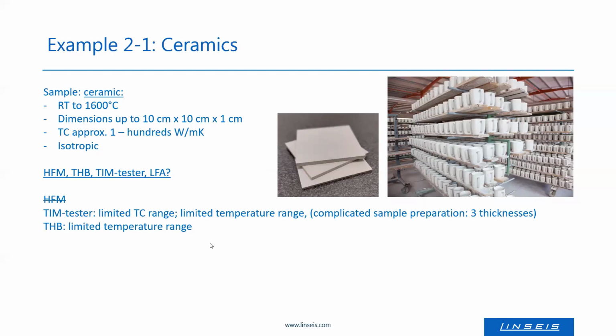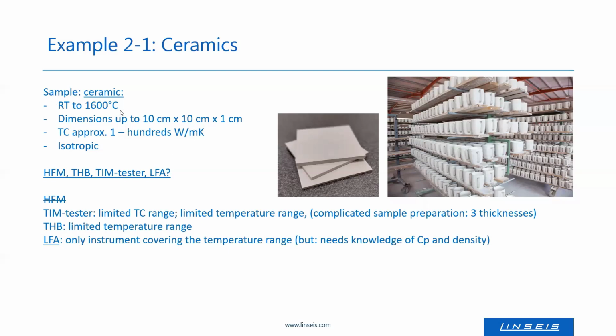THB will not cover the temperature range either, so the laser flash instrument is the only instrument covering the complete temperature range and can handle the dimensions, or you can prepare samples from these blocks which fit to a laser flash analyzer.